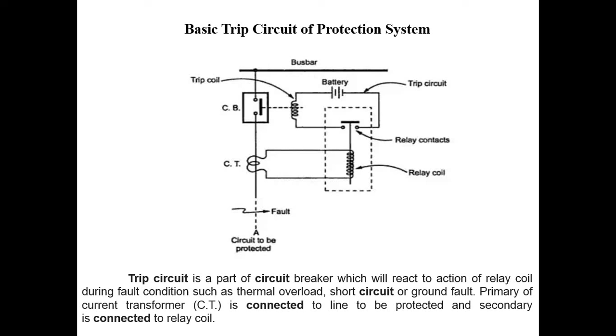The current transformer senses the current flowing through the feeder. The current flowing through the secondary of the CT is given to the relay coil. When the condition is normal, the current flowing through the relay coil is less, so the armature is not affected. When the feeder current exceeds the limit, the secondary current of the CT also increases, so the current flowing through the relay coil increases and attracts the armature. Then the contact closes and the circuit of the trip coil is completed, the circuit breaker trips, and thus the feeder is isolated from the system. So this is a basic trip circuit of a protection system.